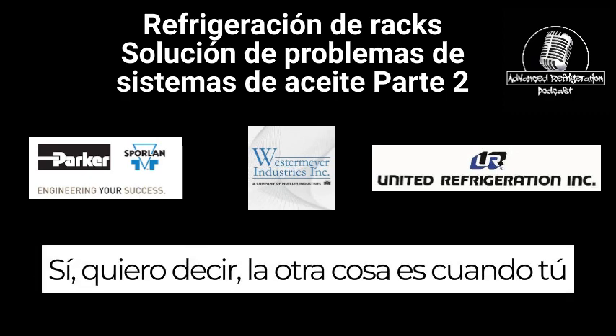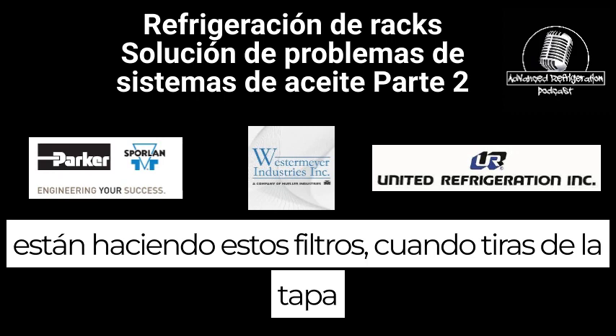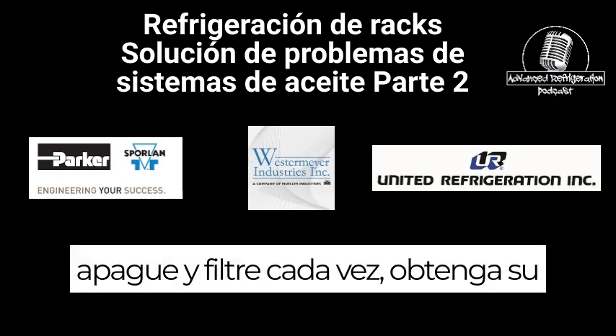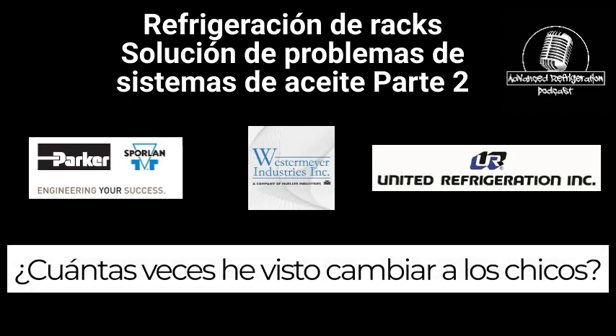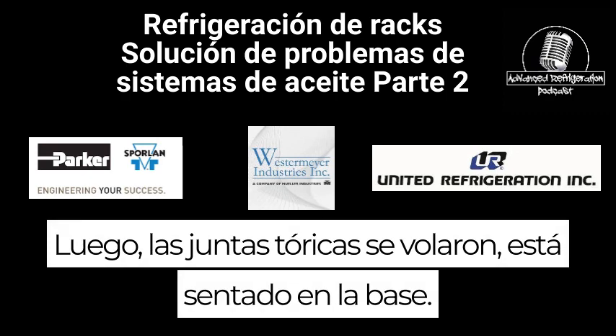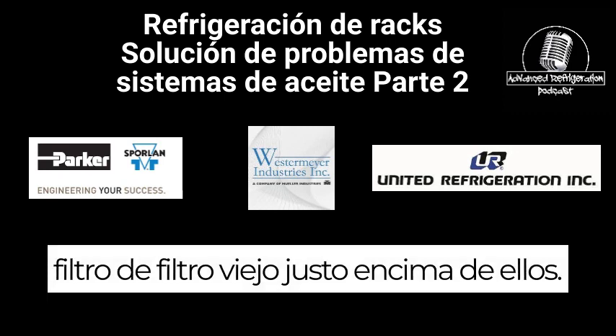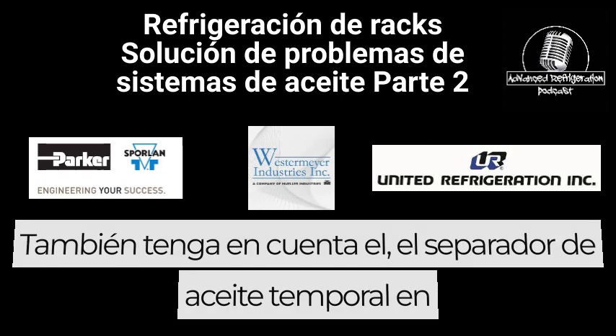Yeah. I mean, the other thing is when you are doing these filters, when you pull the lid off and take the filter apart, every single time get your flashlight out and look down there. I don't know how many times I've seen guys change the filter and they don't pay attention and the O-ring's blown off, it's sitting at the base, or there's two or three O-rings at the base, and they stick the new filter right on top of them, and it's not going to seal because there's three O-rings at the bottom or one O-ring at the bottom.